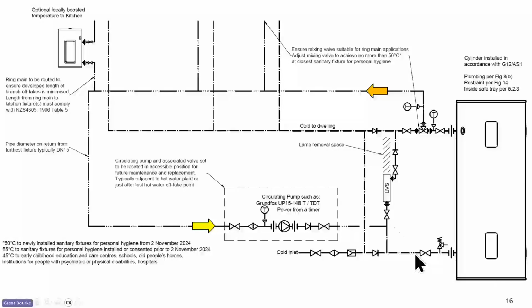Now, when it gets to this leg of the ring main, it's going to split, and it's going to depend on how much heat it's lost. If you had an ideal situation where it lost no heat, all the water would simply go up this bypass and carry around the ring main. But that never happens. So most of the water in a well-insulated system will go up the bypass and go around again, which is why we need to put it through the UV sterilizer to clean it up. A small amount of the water is going to go back to the cylinder.